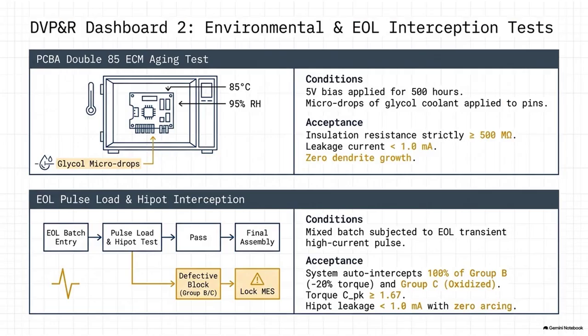Okay, there's one final brutal validation test detailed in the methodology, the high-pot test. High potential testing. This sounds like the ultimate stress test of the physical insulation. It is the absolute final verification of physical safety and containment. They take the fully assembled, fully sealed battery pack and they hit the architecture with 2,500 volts of direct current. 2,500 volts. That is immense. The entire vehicle architecture is only designed to operate at 400 or perhaps 800 volts. Exactly. They hit the system with massive, intentional overvoltage, and they hold that extreme potential continuously for 60 straight seconds.